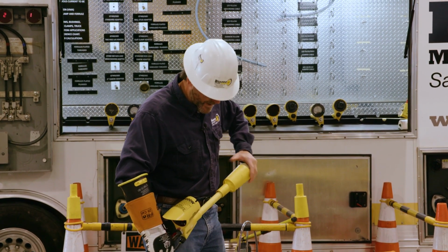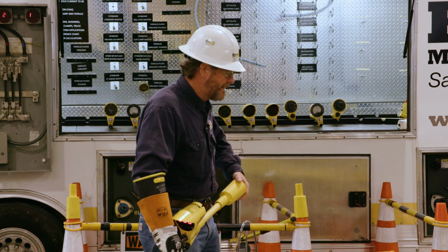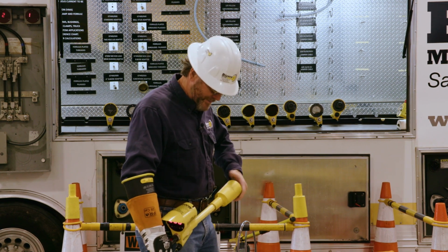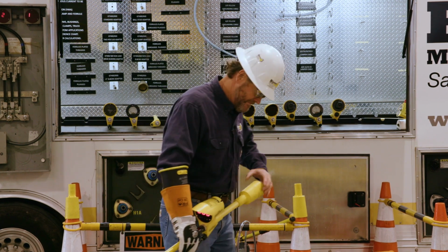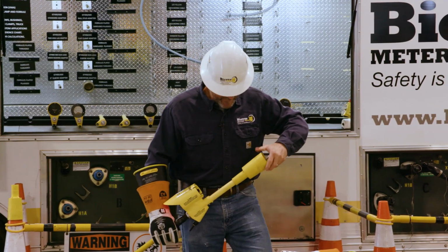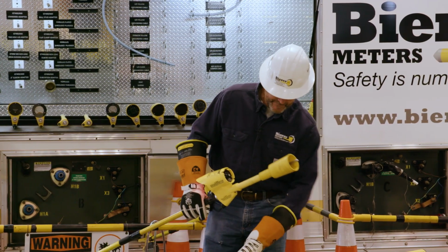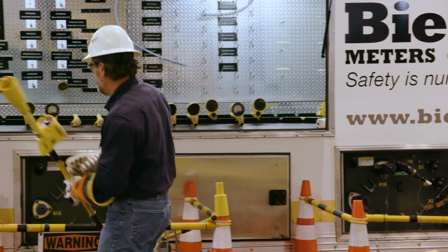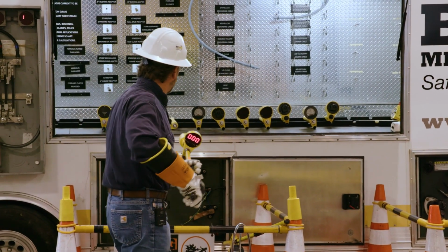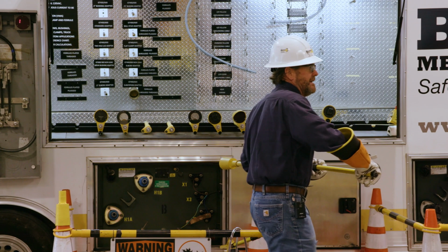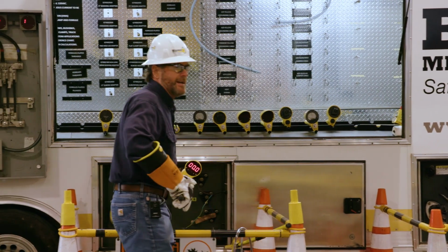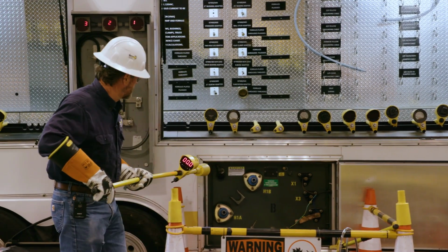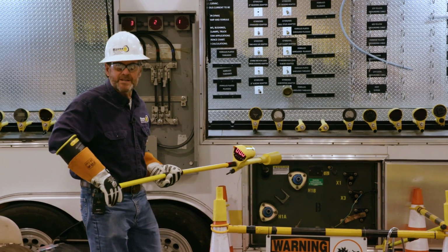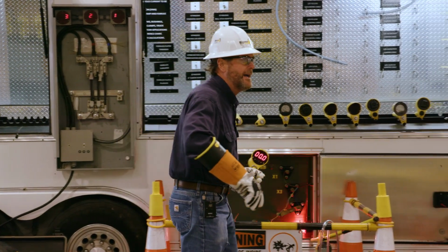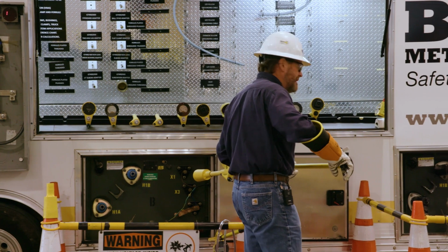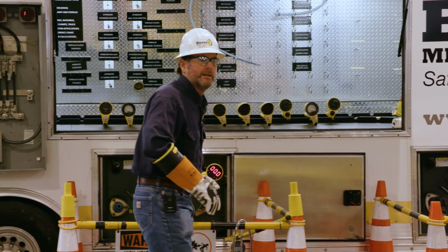So we're going to go to this overhead line with the bushing adapter, making direct contact. If you ever go to a utility or contractor that does not use direct contact tools, you need to have a discussion with the safety guy, the tool guy, the supervisor, and tell them to throw those tools away.